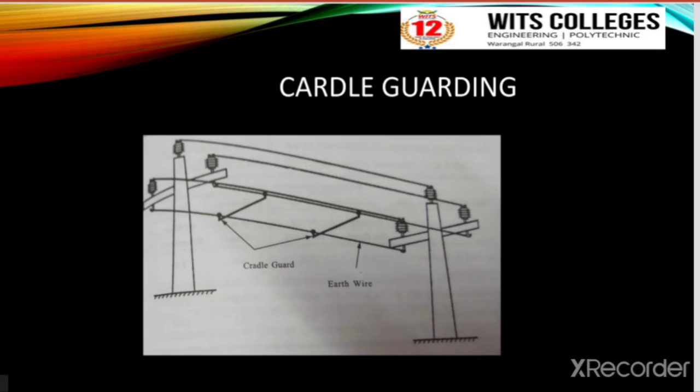Regarding guarding of line crossings, where lines are approaching each other, the Indian Electricity Rule 87 provides all the important guidelines. Whereas Indian Electricity Rule 88 provides that every guard wire shall be connected with the earth at each point at which electric continuity is broken.